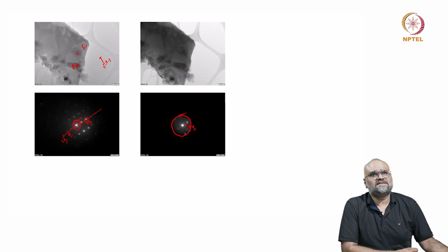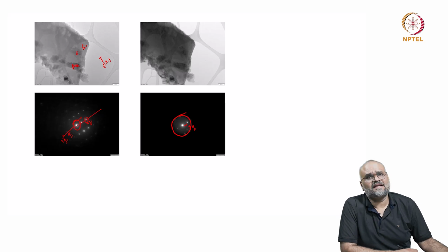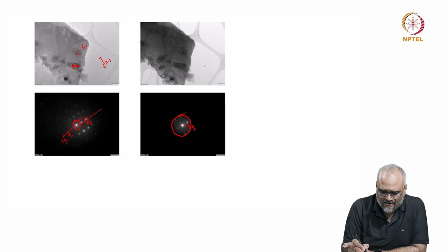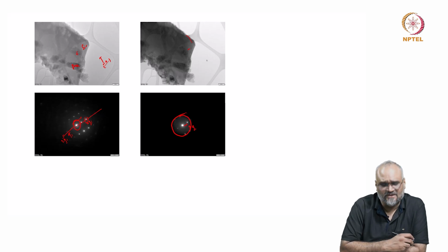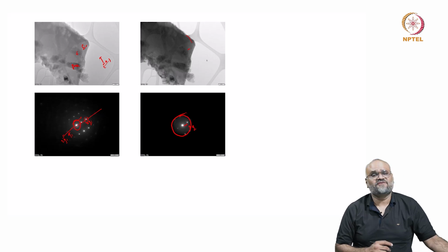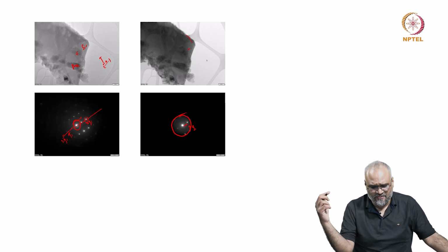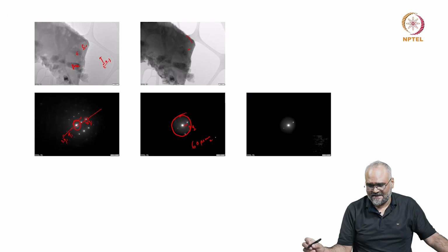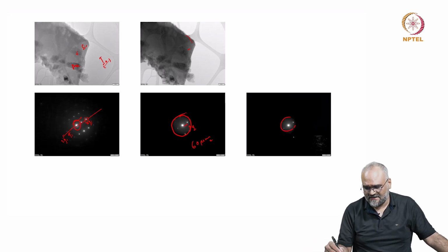When I place the objective aperture and record a bright field image, you can see that the silicon here is appearing darker with respect to the background. Likewise, if I change the aperture again and put in a smaller aperture, so here we put in the 60 micrometer aperture, and in this case we have put in a 30 micrometer aperture. Still the first two reflections are allowed.